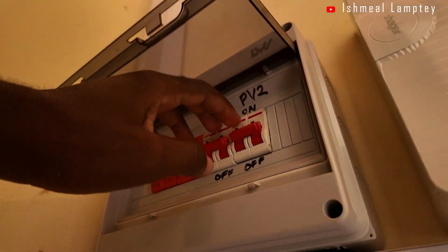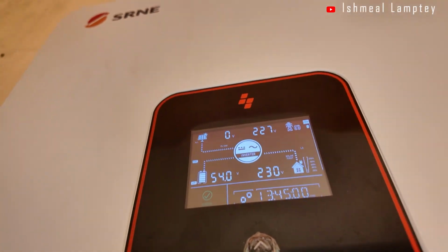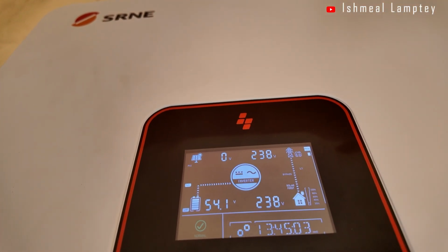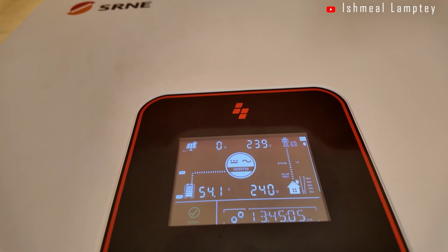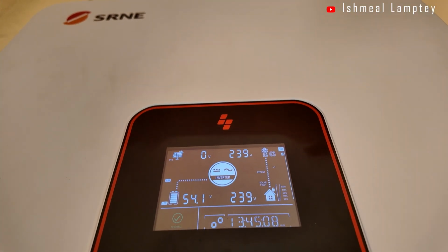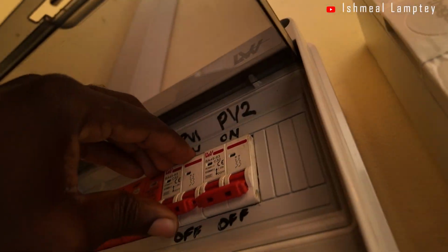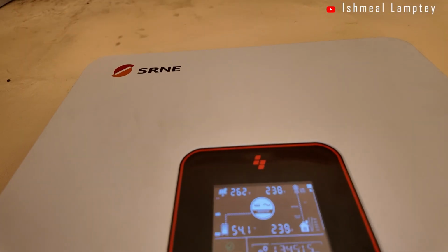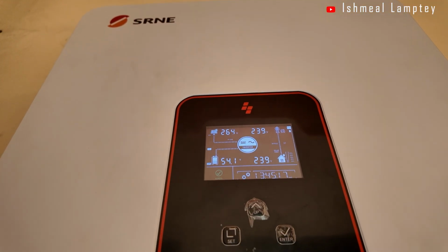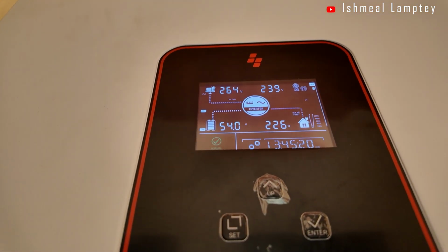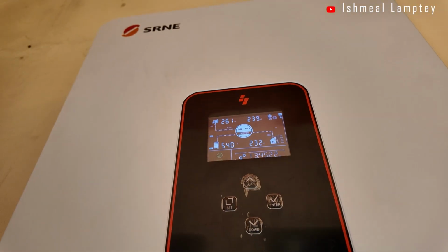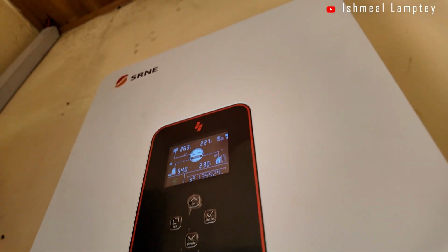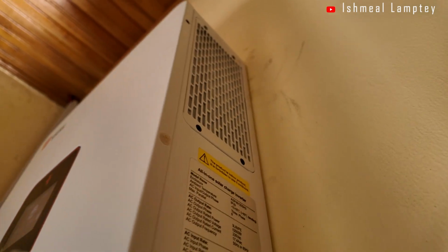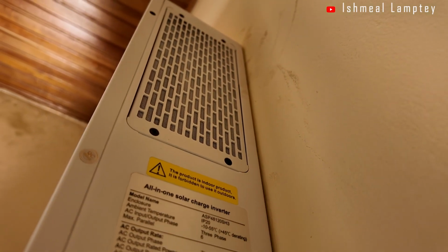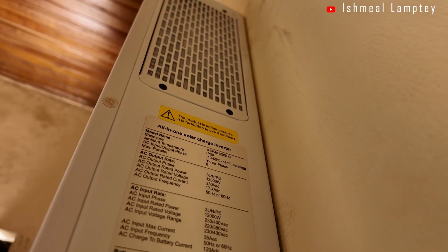Then the second option is having the grid step in once the panel is not able to do that. So on cloudy days where there isn't sufficient power, especially to charge the battery or even to supply load to the house, the grid steps in. Then also in a case where there's a power outage, the battery steps in. Now, one interesting thing I like about this system is that it does all these things in real time. At a point in this video, you see where I was actually testing that, where I turned off the PV, then the grid takes over, then I turn off the grid, then the battery takes over.